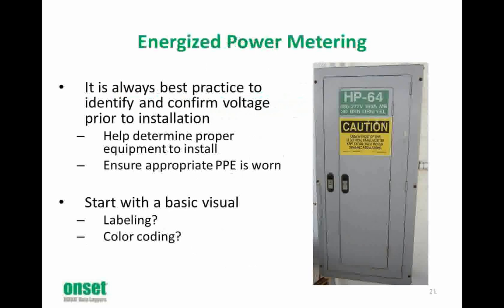Before we install metering equipment in an enclosure, it's always best practice to identify and confirm the voltage we're working with. This will not only help determine what equipment is required, but also ensure the appropriate PPE is worn. The first test should be a basic visual to identify any labeling or color coding. If the enclosure isn't marked with the voltage, we should always assume it is higher, 480 volts in most cases. Once we are wearing the proper PPE, it is safe to remove the cover to gain access to the conductors.